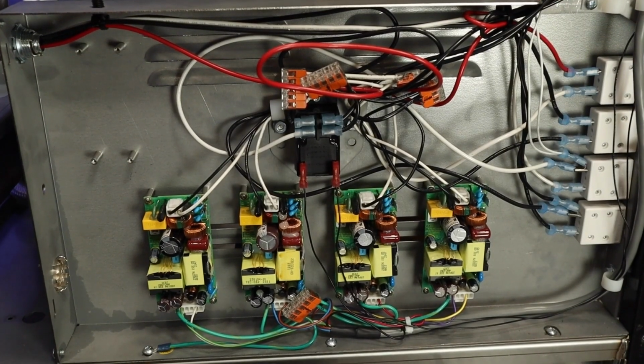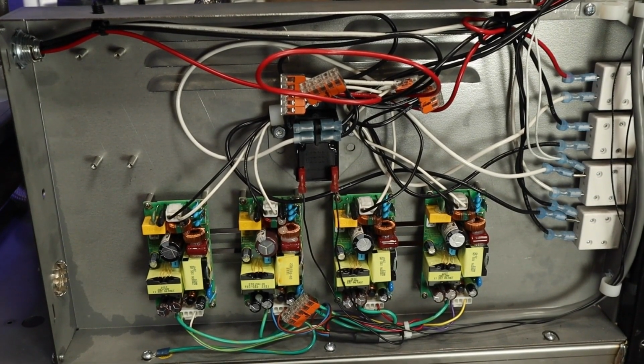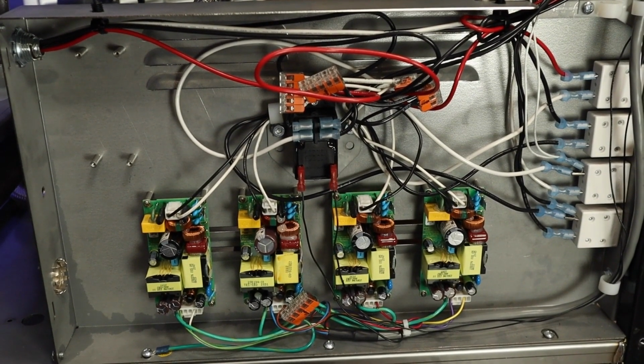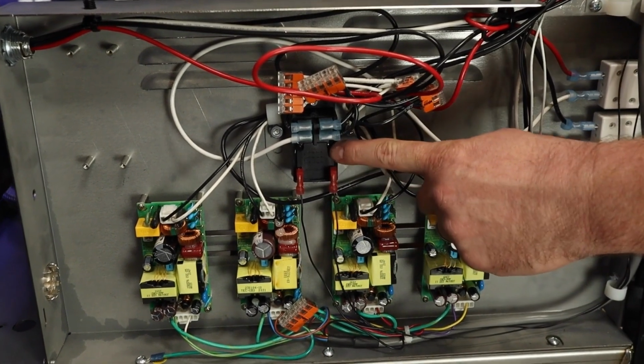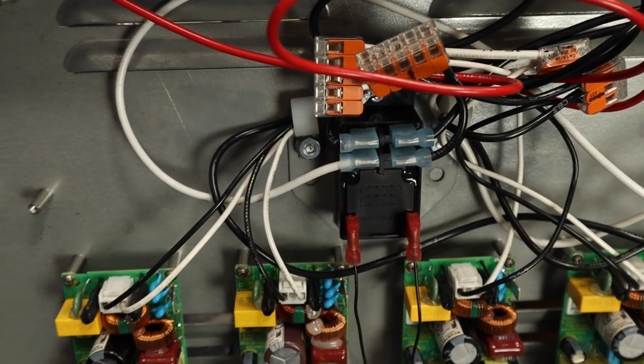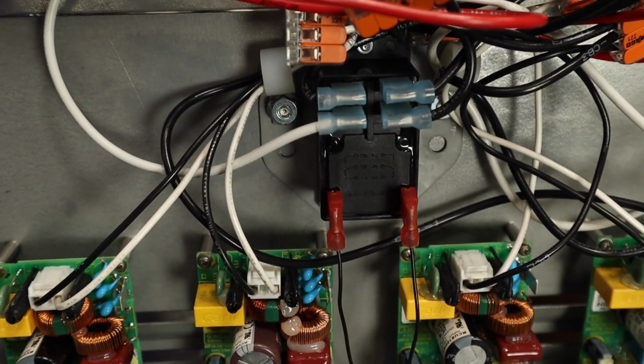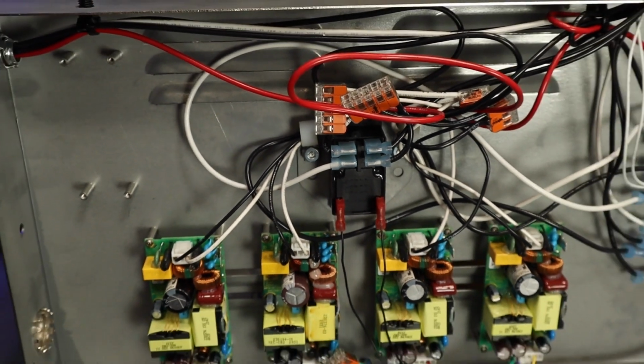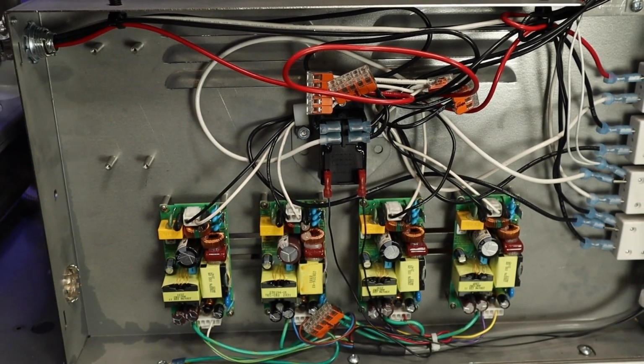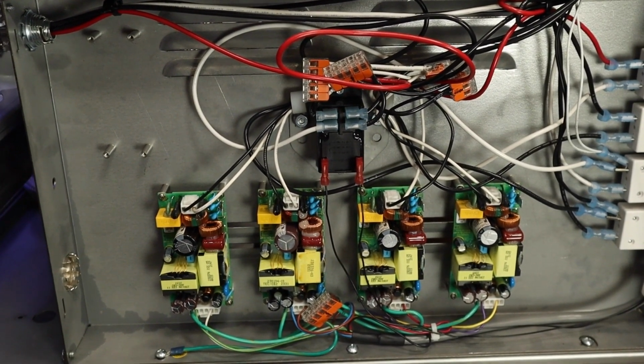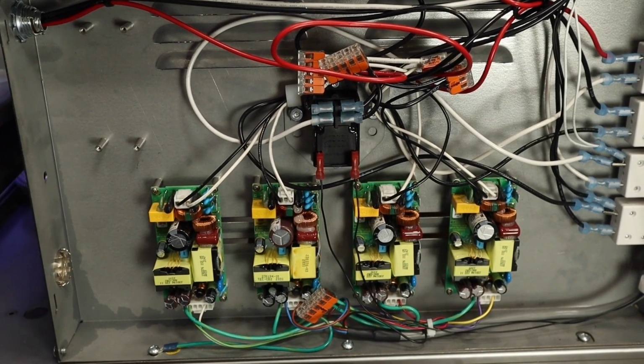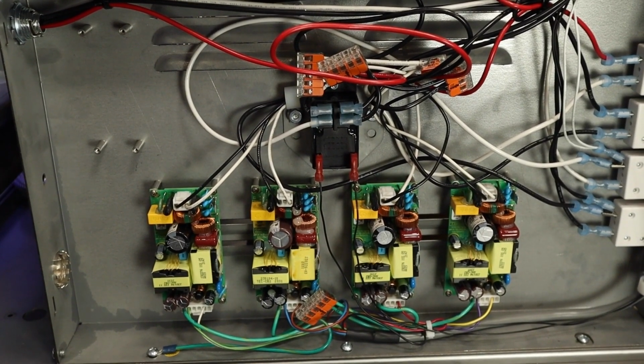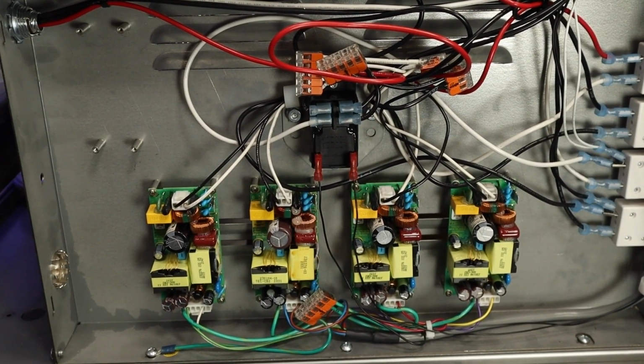If the problem is not with the circuit breakers, then we can remove the left side panel so that we can gain access to our filter pump motor relay. Remember, for 4 vat units, you will have to remove the cover over this enclosure. Now we can go into the control and energize that filter motor again, and then come back over to our relay to check our voltage.